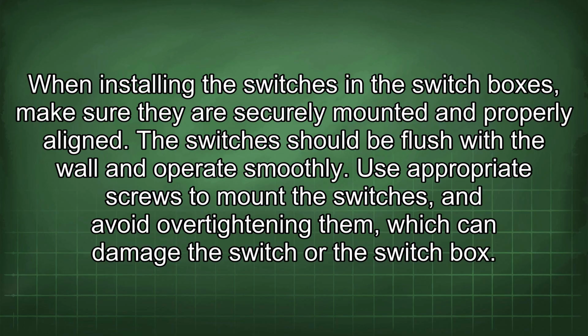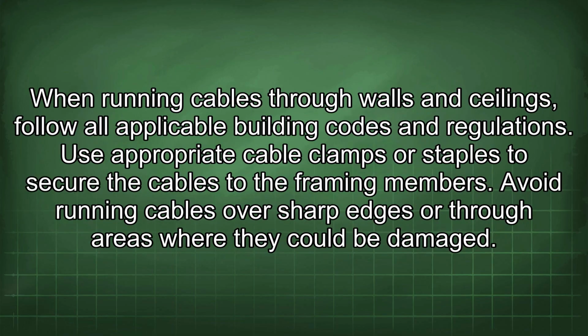When installing the switches in the switch boxes, make sure they are securely mounted and properly aligned. The switches should be flush with the wall and operate smoothly. Use appropriate screws to mount the switches and avoid over-tightening them, which can damage the switch or the switch box. When running cables through walls and ceilings, follow all applicable building codes and regulations. Use appropriate cable clamps or staples to secure the cables to the framing members.